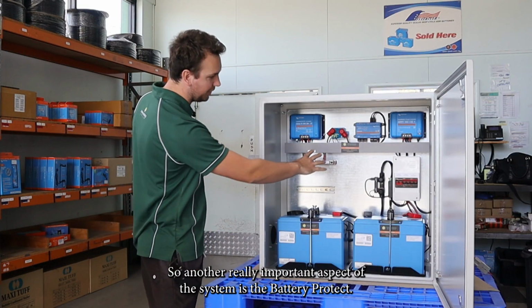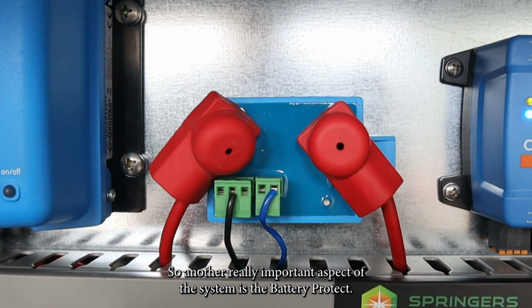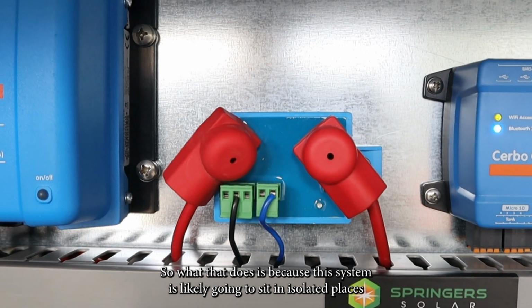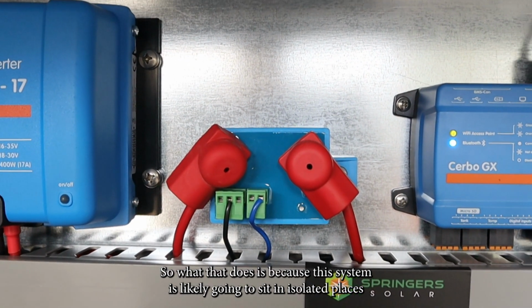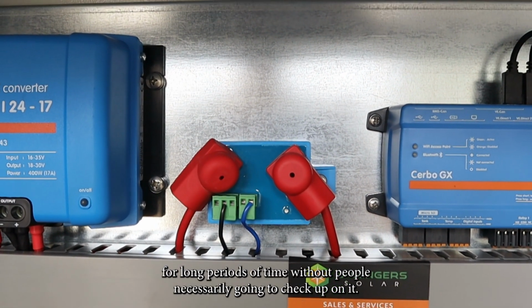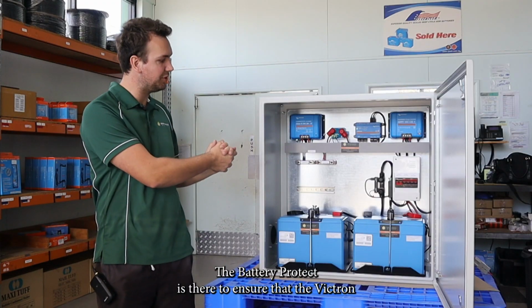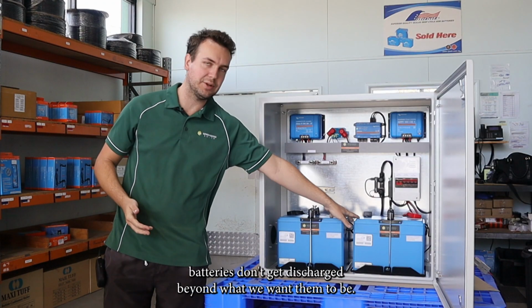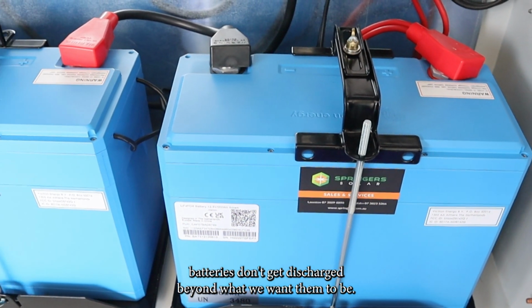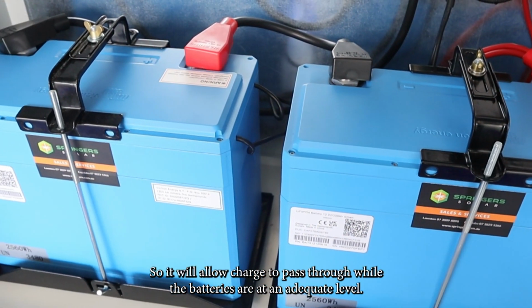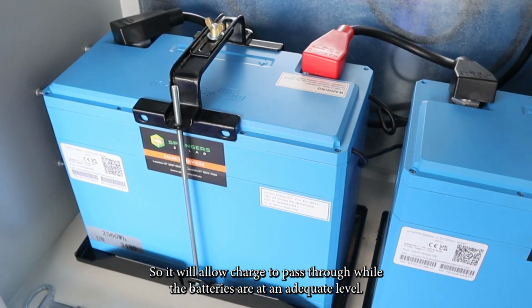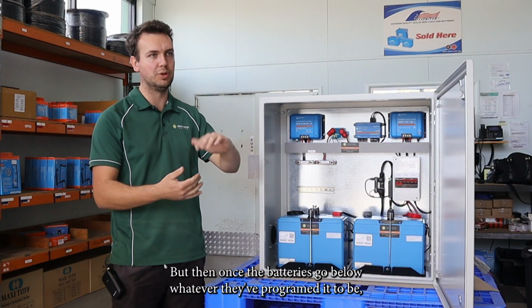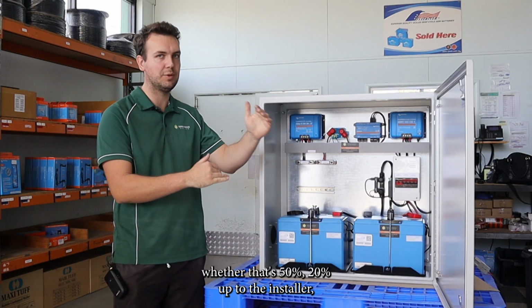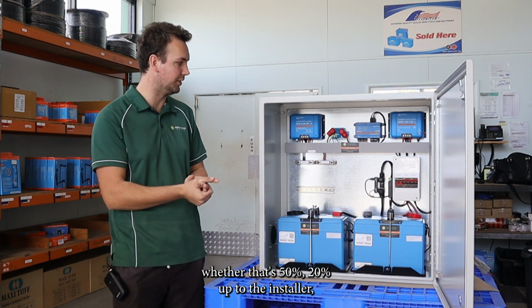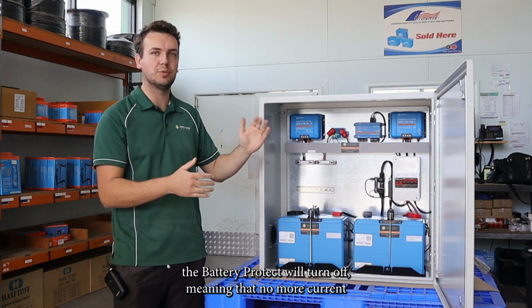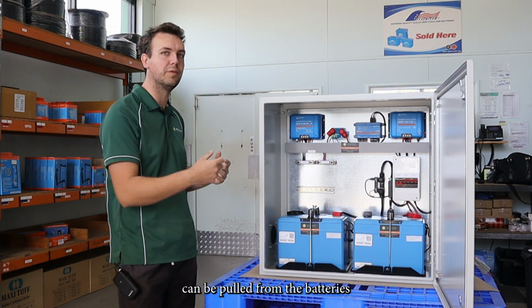Another really important aspect is the battery protect. Because this system is likely to sit in isolated places for long periods without people checking on it, the battery protect ensures the Victron batteries don't get discharged beyond what we want. It allows charge to pass through while batteries are at an adequate level, but once they go below whatever percentage the installer has programmed, whether 50%, 20%, the battery protect will turn off, meaning no more current can be pulled from the batteries.